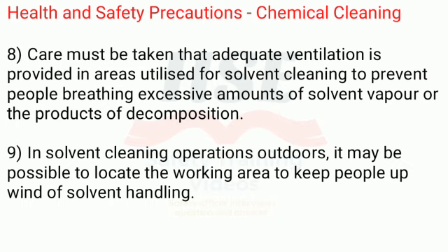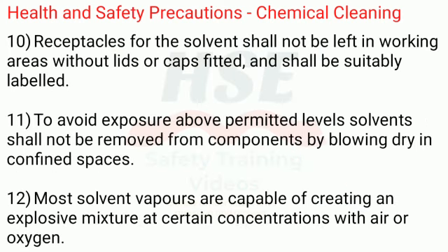9. In solvent cleaning operations outdoors, it may be possible to locate the working area to keep people upwind of solvent handling. 10. Receptacles for the solvent shall not be left in working areas without lids or caps fitted, and shall be suitably labeled. 11. To avoid exposure above permitted levels, solvents shall not be removed from components by blowing dry in confined spaces.